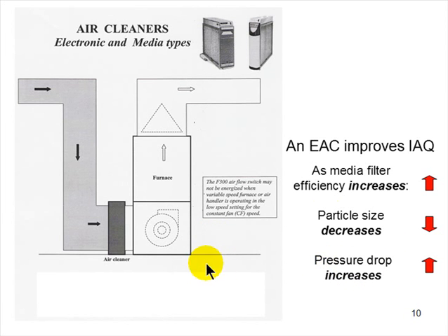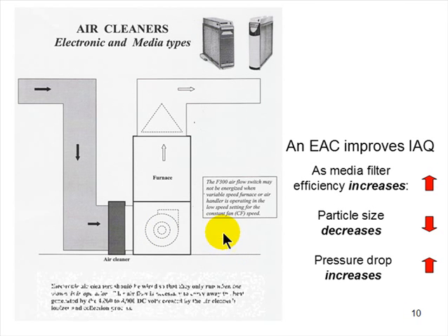You understand all that? Now, if you want to back up and say, okay, I'm going to make this thing a chain link fence, and I'm not throwing bowling balls at it, I'm going to throw golf balls. Well, about half the golf balls are going to go through, and about half are going to bounce back. But in the real world, they don't get to bounce back. They'll just impinge. They call it viscous impingement. They'll be pressed up against that media filter, and more will collect. And the opening, the air flow through this, will get smaller and smaller. The air flow will reduce because the pressure will increase. So you have the same symptoms. It just takes longer for it to happen.